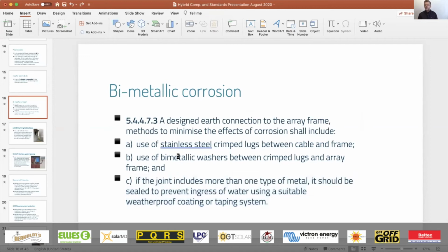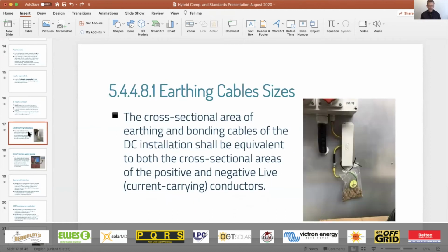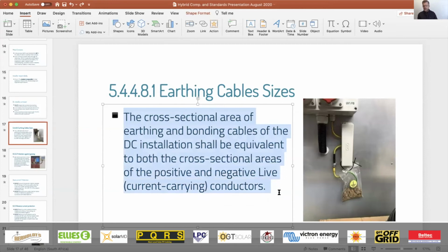Guys, we are going to see loads and loads of bimetallic corrosion issues in the solar installations, because there are lots of guys that are busy connecting a copper conductor to the aluminium frame of the solar modules. The cross-sectional area of the earthing and bonding cables of the DC installation shall be equivalent to both the cross-sectional areas of the positive and negative live conductors.